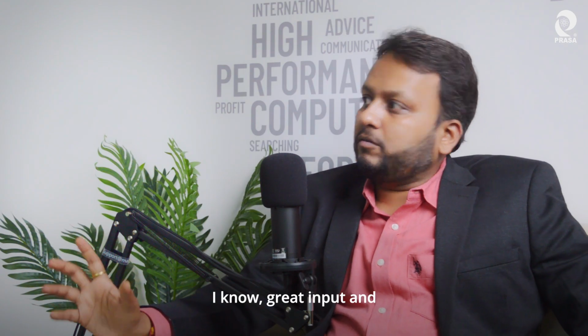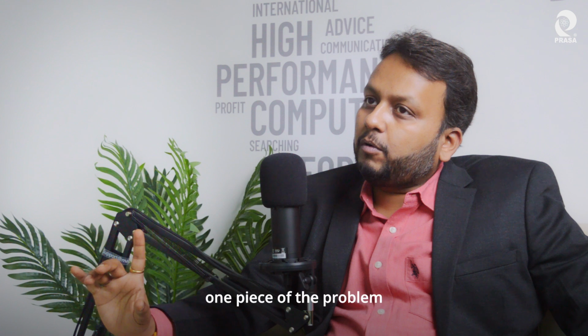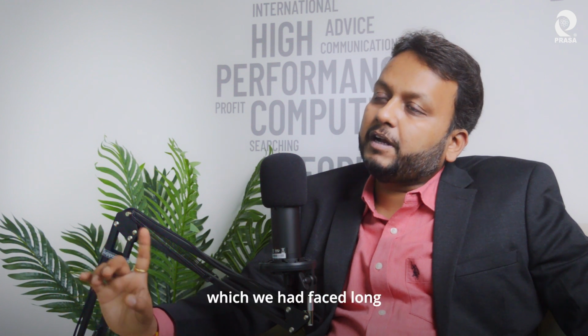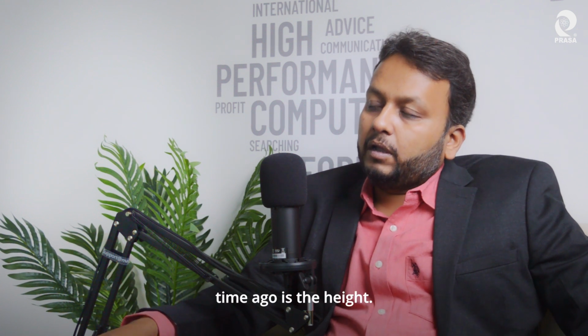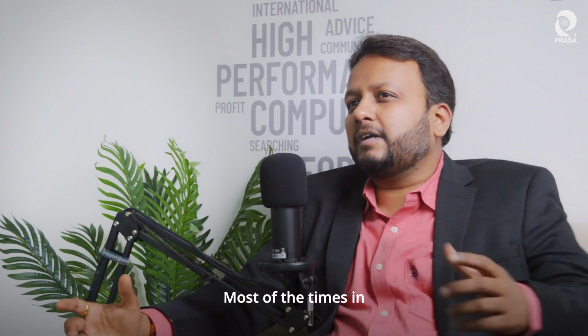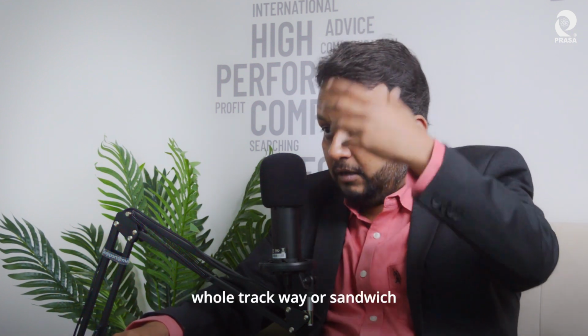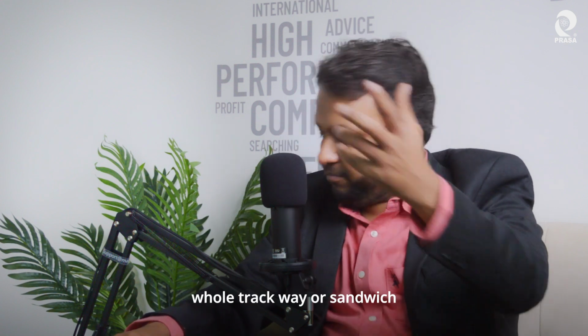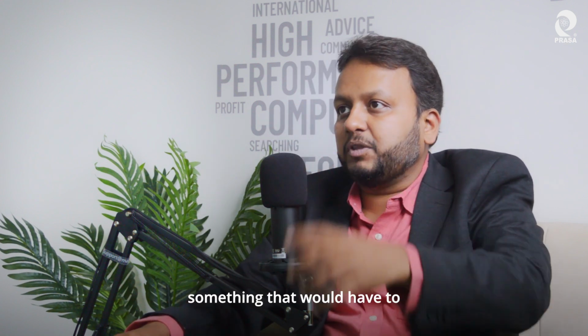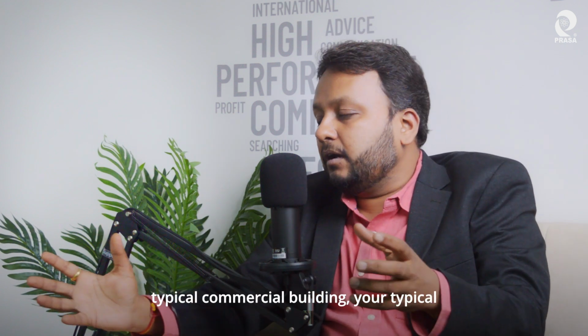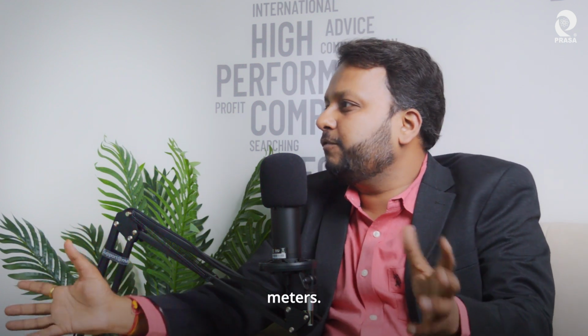Great input, and I wanted to talk about one piece of the problem which we had faced a long time ago, which is the height. Most of the times in data centers, height becomes one of the major criteria, because now this whole trackway or sandwich or air insulated would have to be installed on top of the rack. And if we are building a data center in a typical commercial building, your typical height is about 3.5 meters.